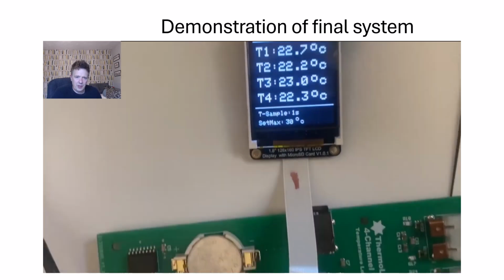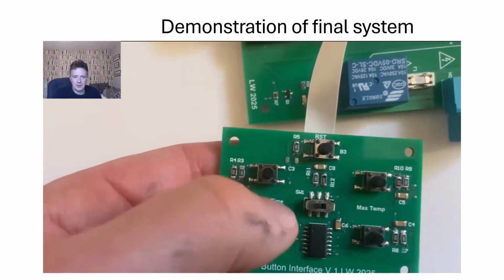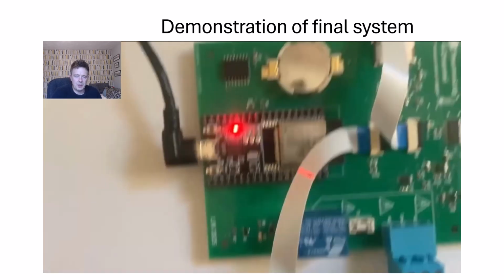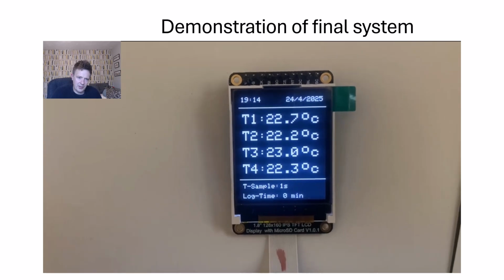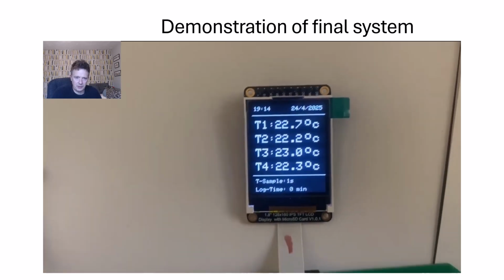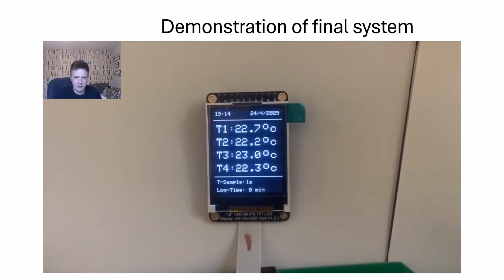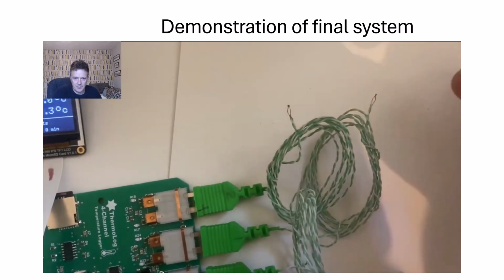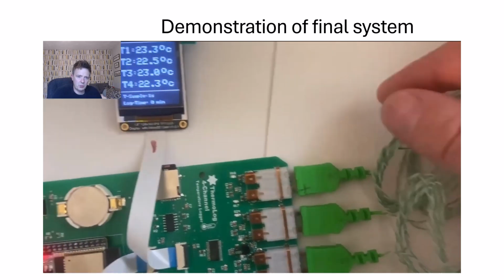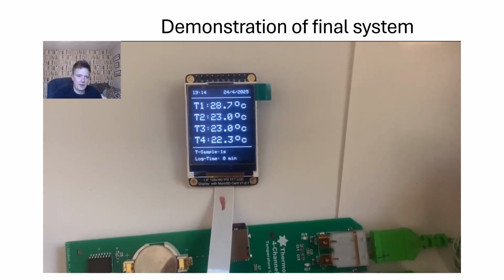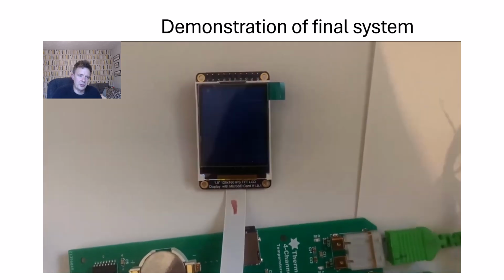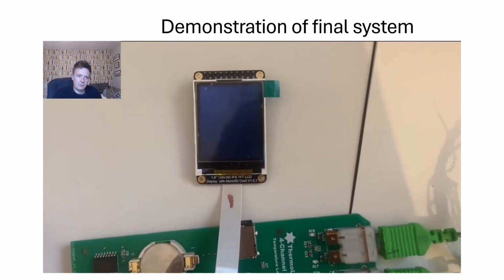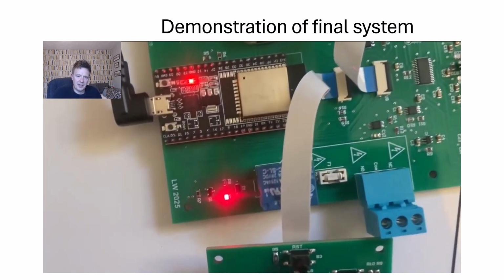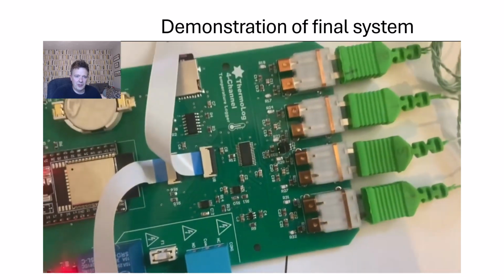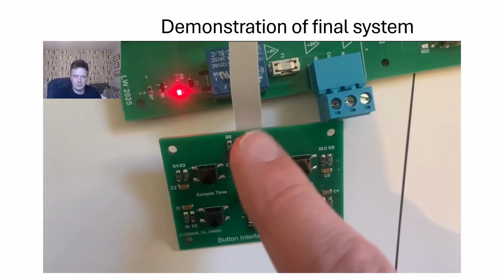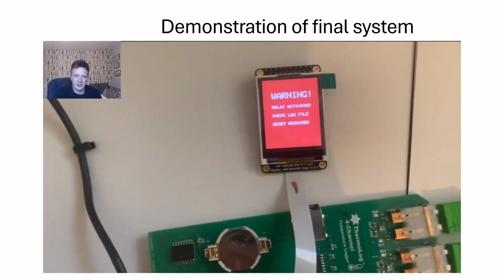There you go. So what we do now, we'll start system logging. We'll do the center switch to the right to put it in login mode. As you look down the bottom now, you should see that we're actually logging, and it will tell on the LCD how long you've been logging in minutes, which I think is quite a useful feature. So we go on, just about touch channel 1, I believe. Yes, there you go. And that's the relay activating. That gives you a warning sign on the LCD. The relay will only disengage if the system is reset, and that is a safety feature because you don't really want the system to keep being switched on and off while the temperature lowers.